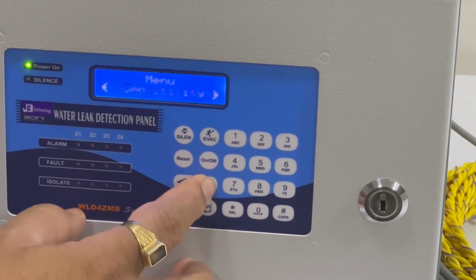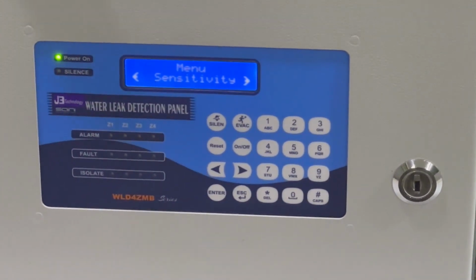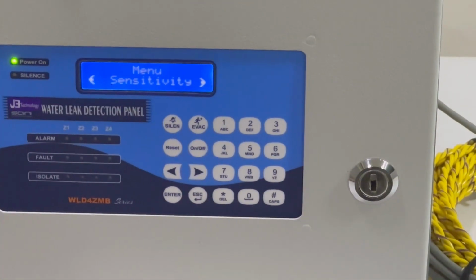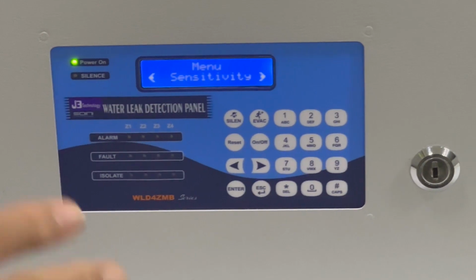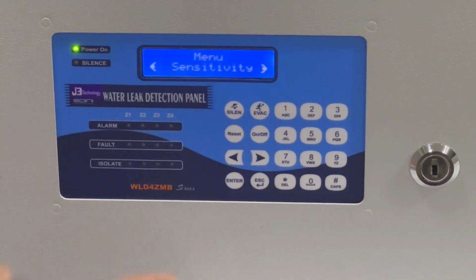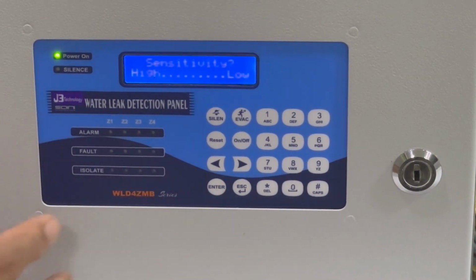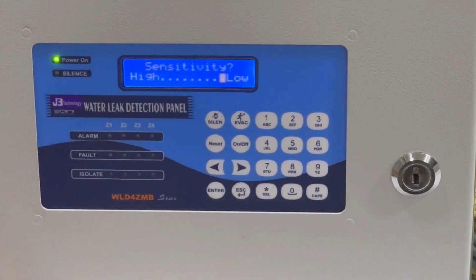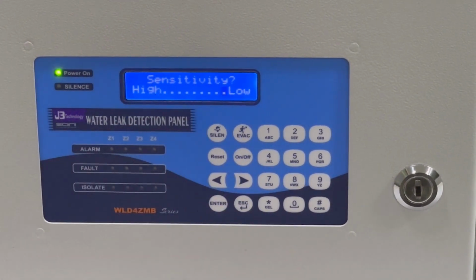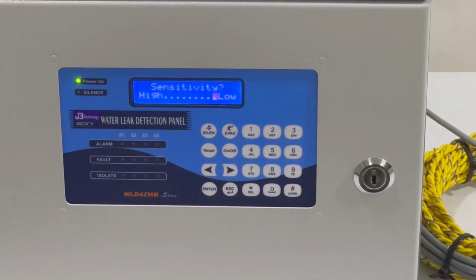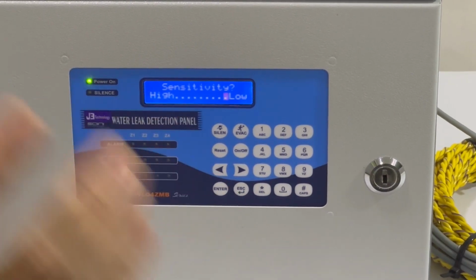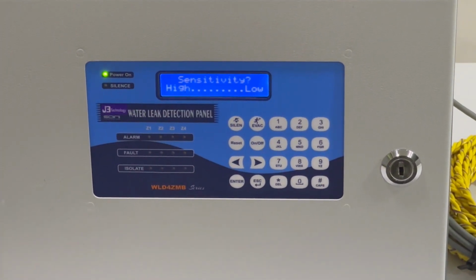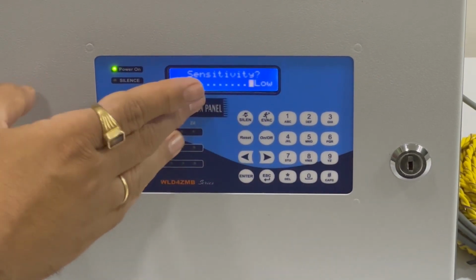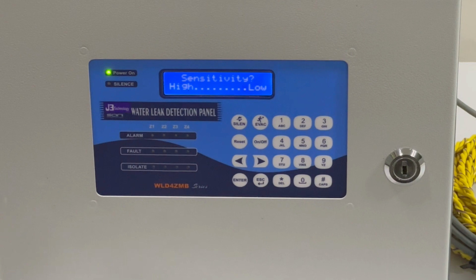Okay, now zone setting. Now the very important part is the sensitivity. You can set the sensitivity of the sensor cable according to your environment, according to your room, or as per the client requirement. It's a very important part. Just go to sensitivity and press enter. You can see on the display there is high and low sensitivity. This means you can set the sensor cable with high sensitivity or low sensitivity. Where you think there will be a chance of false alarms, you can set this sensor cable to low sensitivity, because for normal moisture it will not alarm. For high sensitivity, where there is moisture also, there is a chance of alarm.